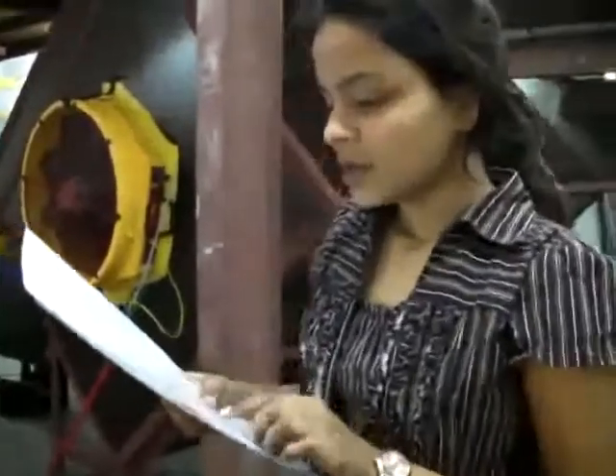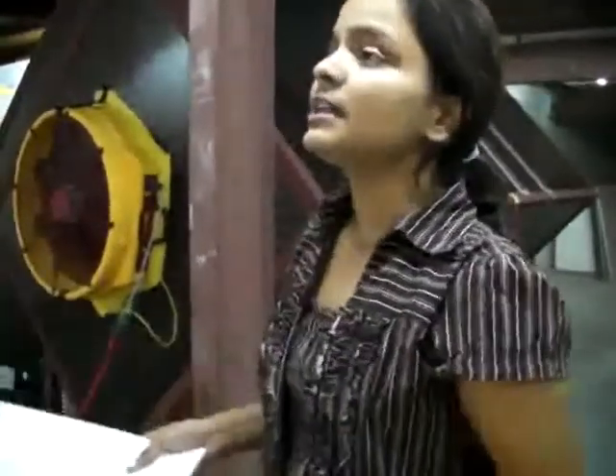Now the fan in the B range is fixed and is ready for calibration. Before calibration, ensure that the calibration procedure is in hand. Ensure that the door to the warehouse where the calibration is to happen is closed at all times to avoid any external disturbance such as wind and rain. Make sure a 2-meter clearance is maintained in front of the fan and in front of the conical nozzle.